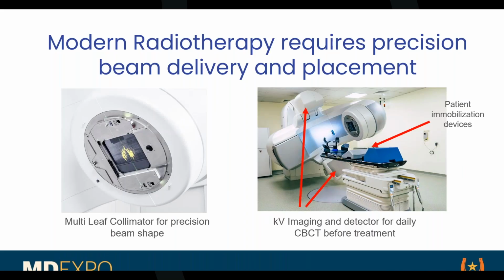We have a treatment couch, which has to elevate the patient to the right distance. It also positions the patient the right way. It rotates as well. If you see down over here, there's a rotating plate, so we rotate it that way as well. So we really want to use geometry to our advantage to have the beams come in from exactly the right angles in order to get the right dose distribution.